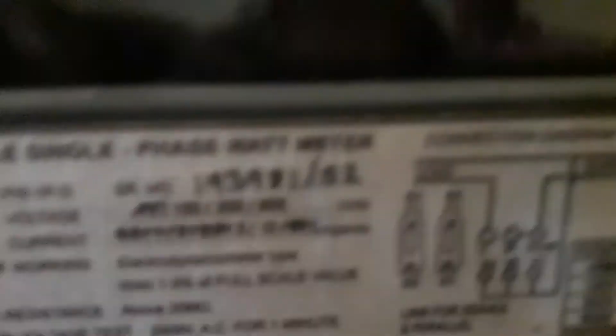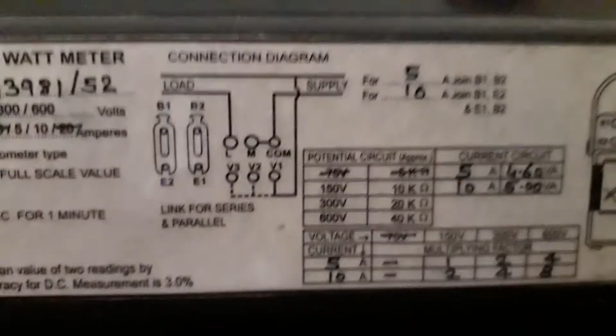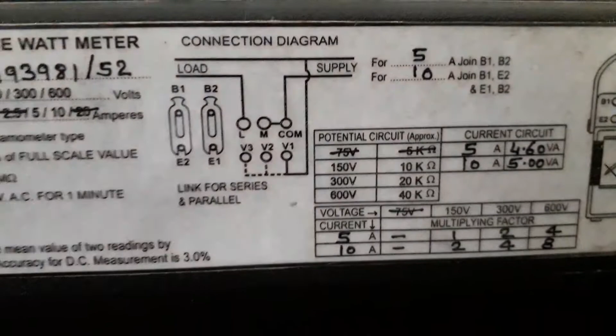Now how to calculate this? See here in the wattmeter connection diagram, with the terminals B1, E2 and B2, E1, that connection is for 5 amps. For 10 amps, how to calculate? The multiplication factor is this: for the 5 amp range, if we choose 150 volts, the multiplication factor is 1.